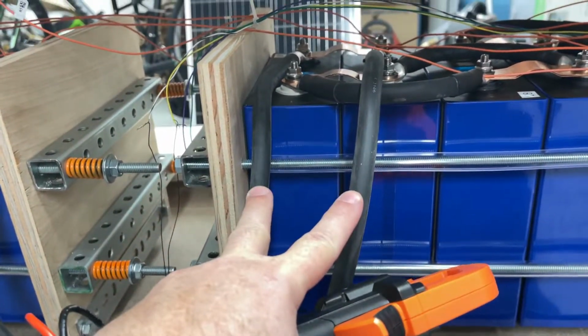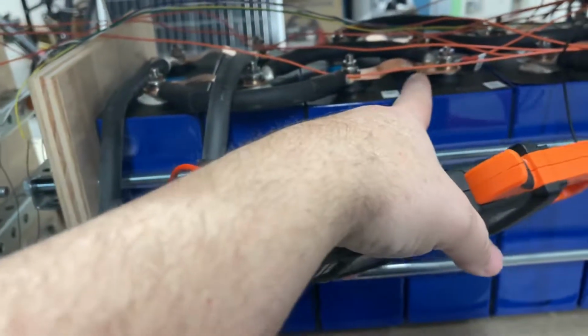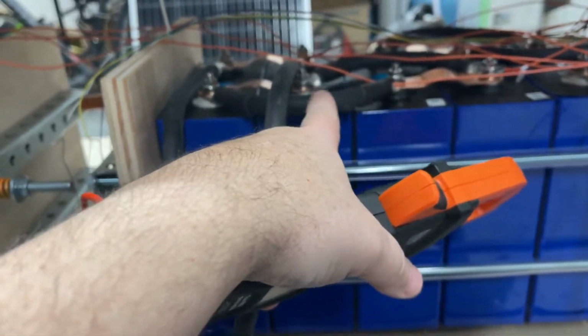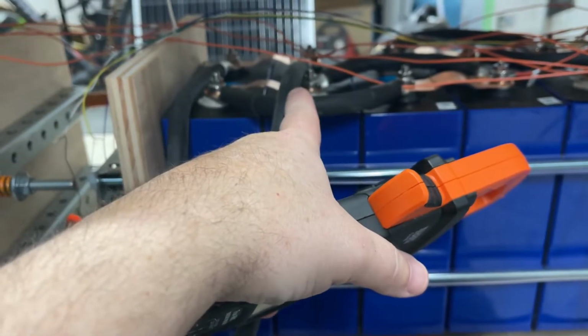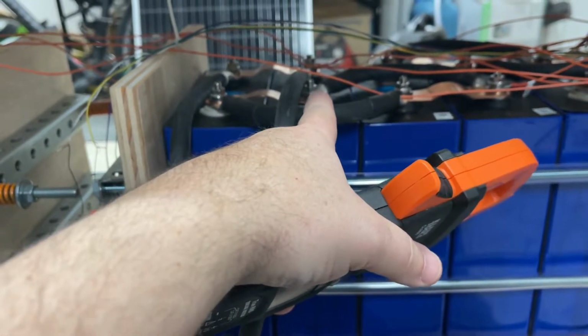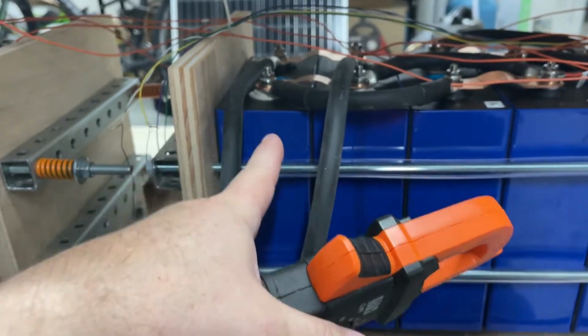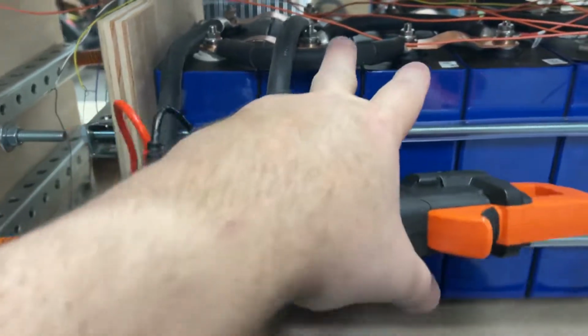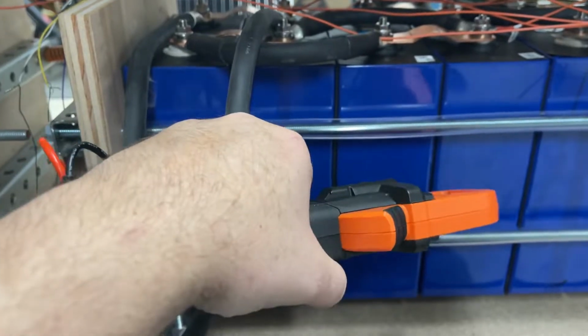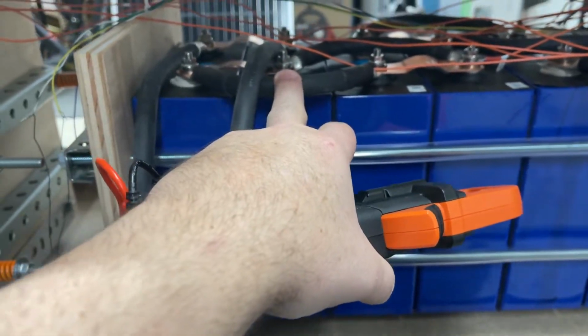The way I've wired my batteries is a little different than most. Most people will just run bus bars for the parallel and run another bus bar for series, and that ends up creating a bit of an imbalance between how much is being pulled from this cell versus how much is being pulled from this cell. So what I'm doing is actually wiring both of these together in such a way that hopefully all the current is pretty well balanced between all of them.